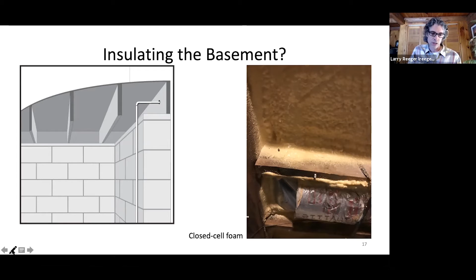The last thing we're going to talk about right now is the vapor barrier, since we're still in the basement. This is an example of fiberglass insulation in the ceiling of the basement. We've said this basement isn't part of the envelope, and everything above that floor, that ceiling, is part of the envelope. You'll see there's a problem here. A vapor barrier, or more accurately a vapor diffusion retarder, is a material that reduces the rate at which water vapor can move through a material.